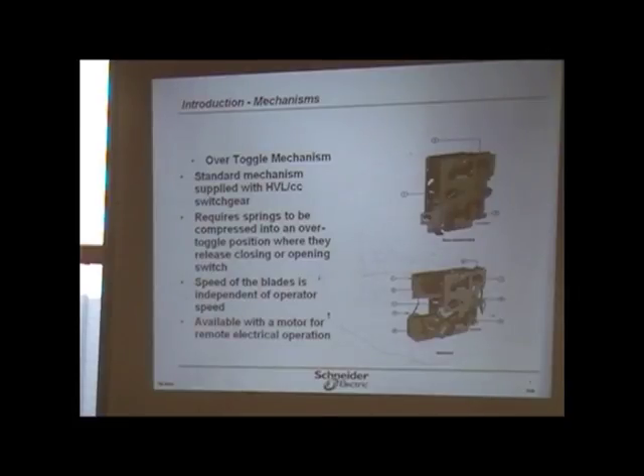It's also available with a motor, for electric operation. There's that encased. That's more or less like a cutaway side view. Number 2 is the fixed contact. Number 3 is a switching blade. Number 4 is the operating shaft that closes the blades, so it's all 3 blades at one time. And number 1 is the epoxy housing.